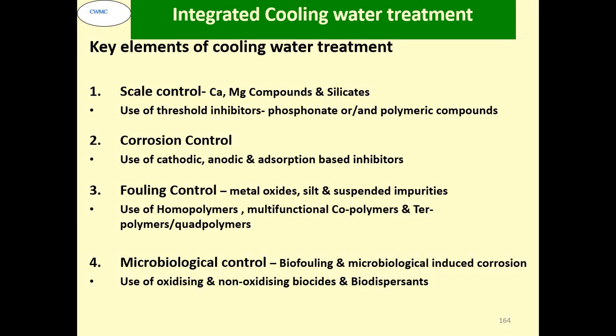Corrosion control by using cathodic, anodic and adsorption based inhibitors. Fouling control is for metal oxide, silt and suspended material, using homopolymers, multifunctional copolymers or terpolymers, quadpolymers, etc. Microbiological control, biofouling and microbiologically induced corrosion, by use of oxidizing and non-oxidizing biocides and biodispersants.